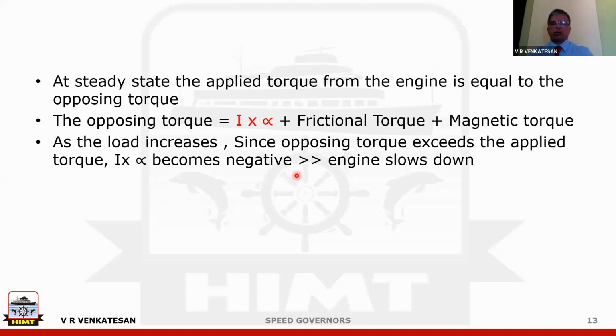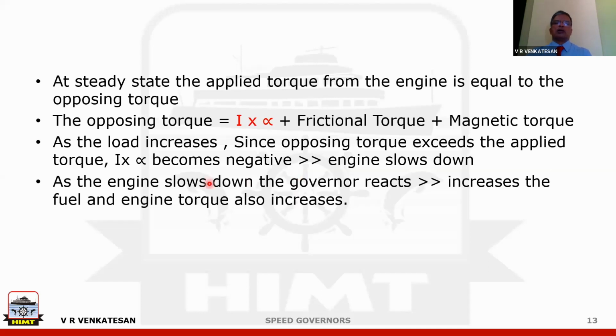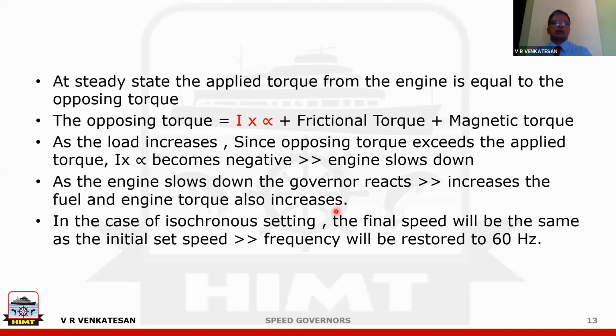Once the engine slows down, the governor will react. When the governor reacts, it increases the fuel and the engine torque will increase. Once again, it can restore the balance. But the issue is what will be the speed. In the case of isochronous, the final speed will be the same as the initial speed. The frequency will be 60 Hertz.